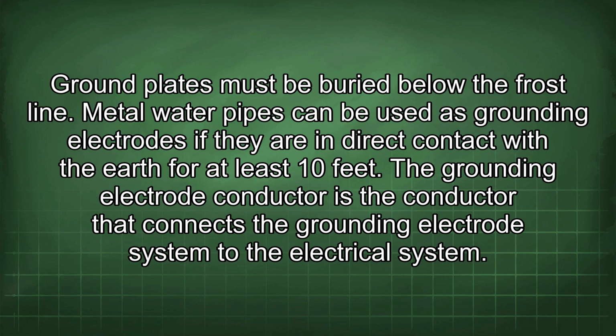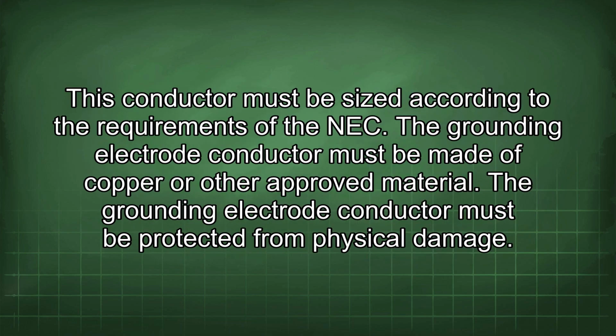least 10 feet. The grounding electrode conductor is the conductor that connects the grounding electrode system to the electrical system. This conductor must be sized according to the requirements of the NEC. The grounding electrode conductor must be made of copper or other approved material. The grounding electrode conductor must be protected from physical damage.